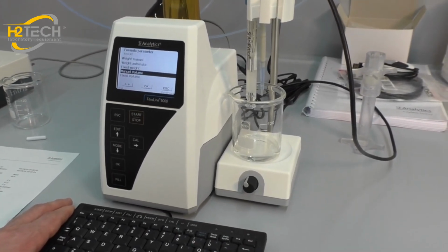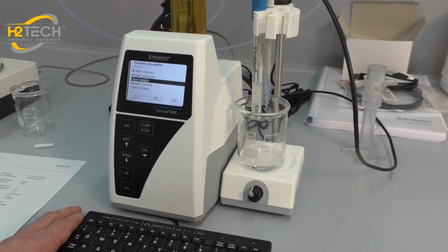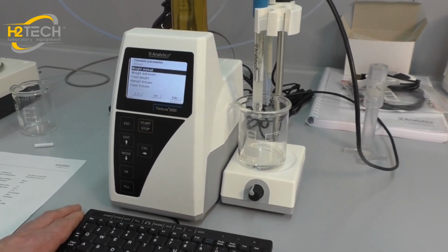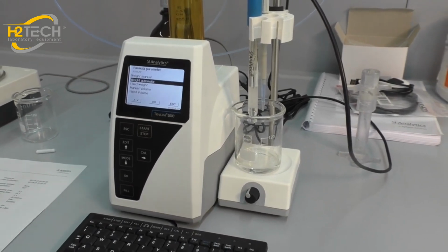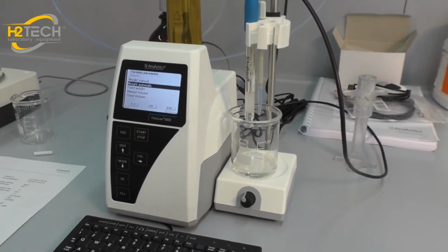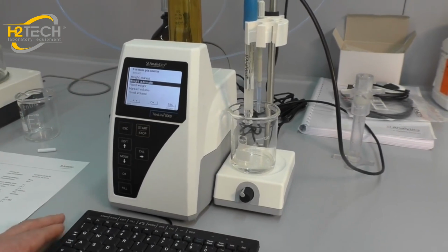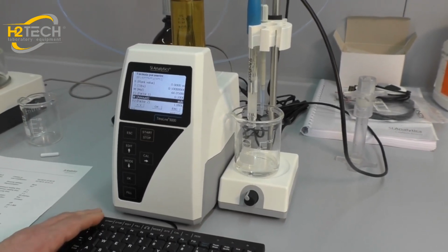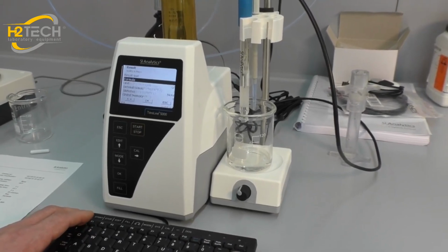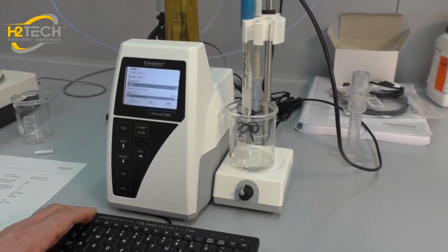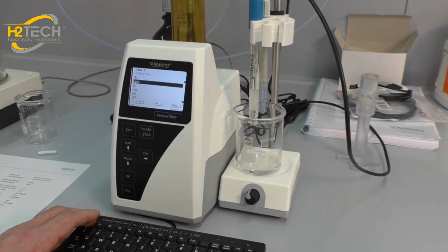The volume is changed to weight manual or weight automatic, because we are now using a balance, and the balance is connected to the Titroline 5000. We can also use weight automatic, and that's it.